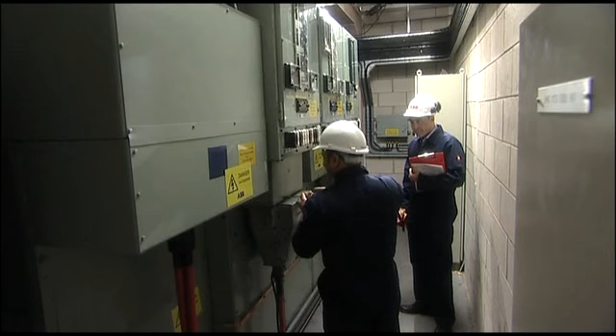It is sometimes impossible to be sure that even connections under cover are safe. There may be an error in earlier steps, or the connections may have a dangerous voltage induced from nearby power equipment. By removing the cover, you are in a situation where a slip or accidental movement could result in contact. You must take special precautions, for example, by wearing insulated gloves.